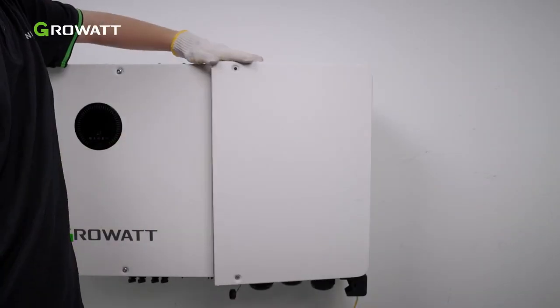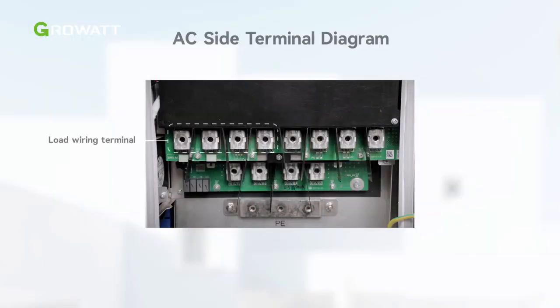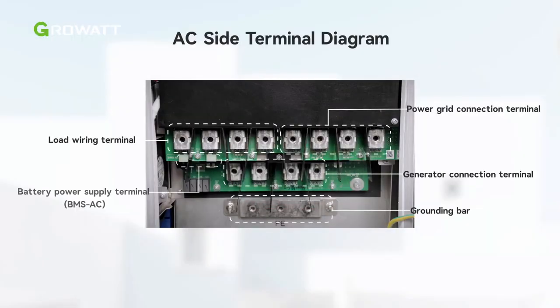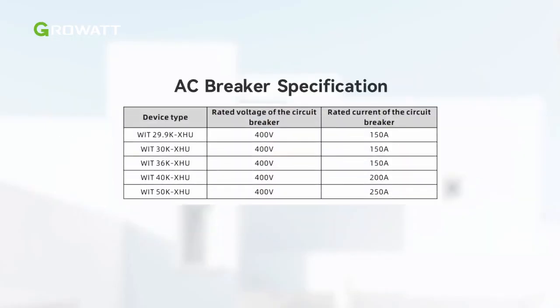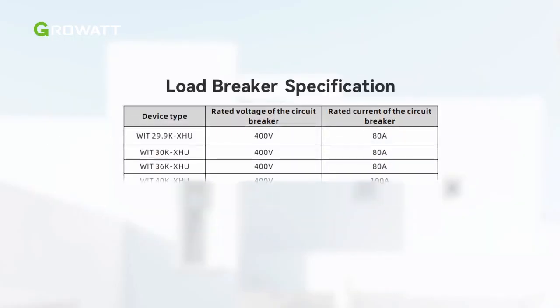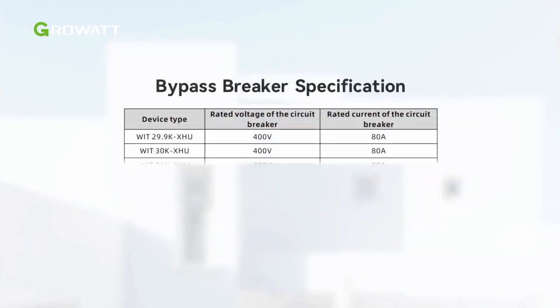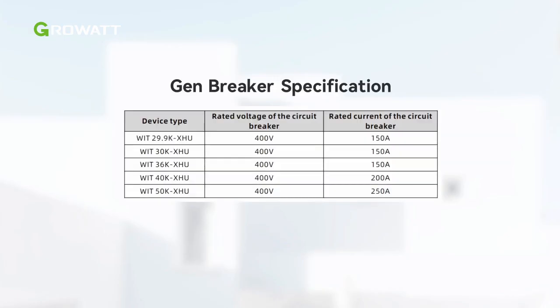Remove the right cover plate to start the AC terminal wiring. Before wiring, check the following AC terminals behind the cover plate. The rated circuit breaker and power cable specifications are illustrated in the table. Please choose the appropriate breaker or cable according to the inverter model.